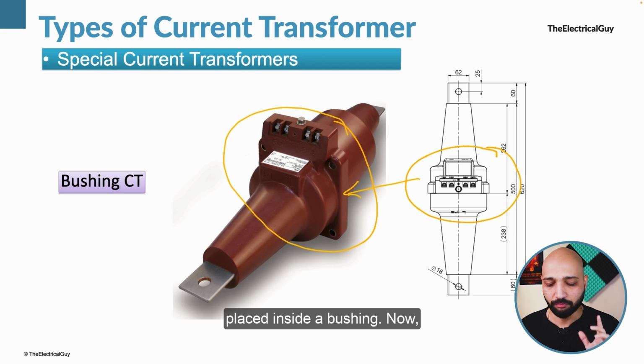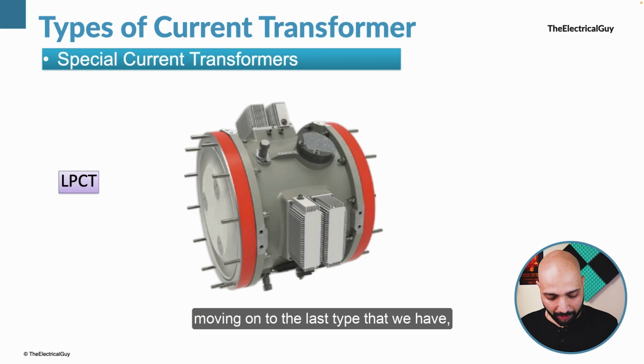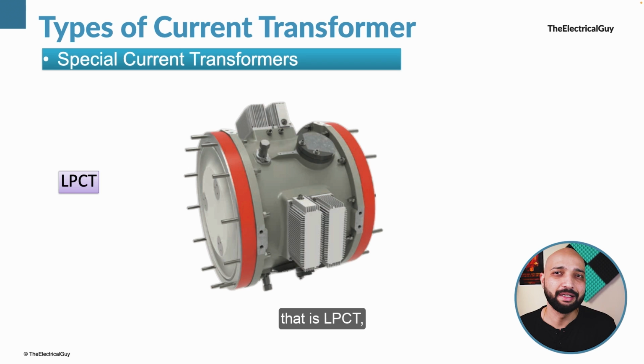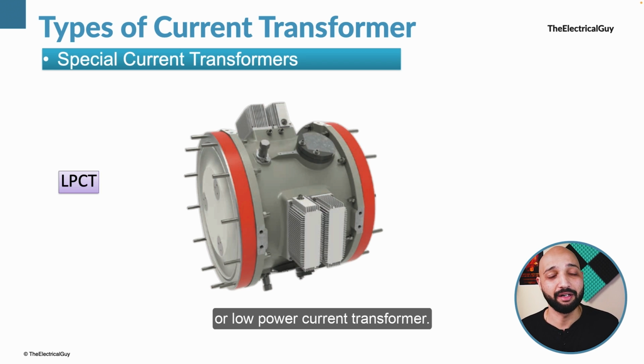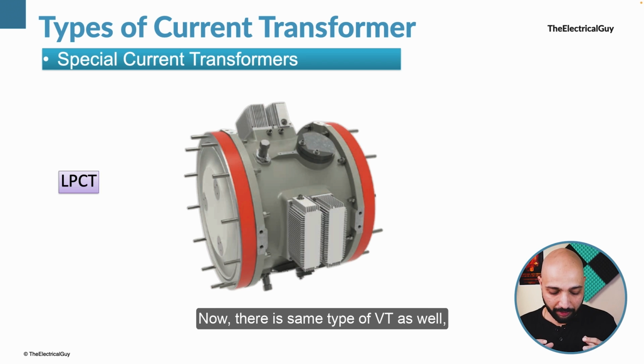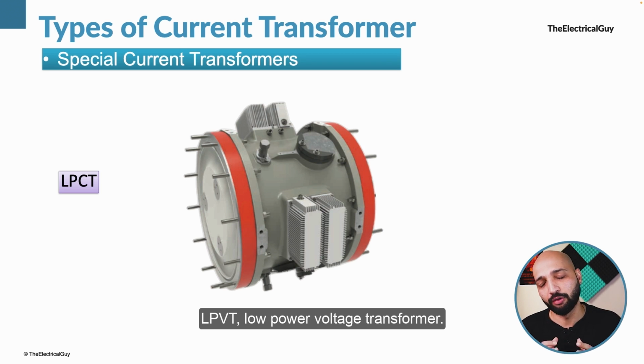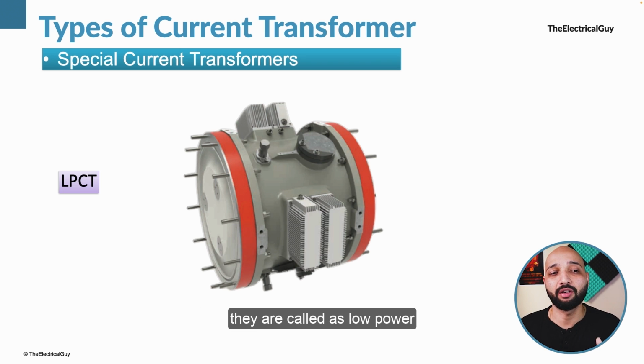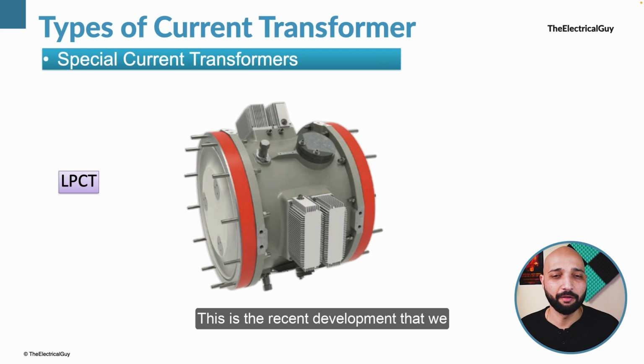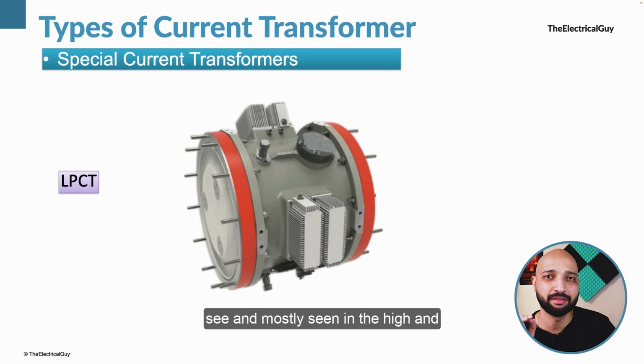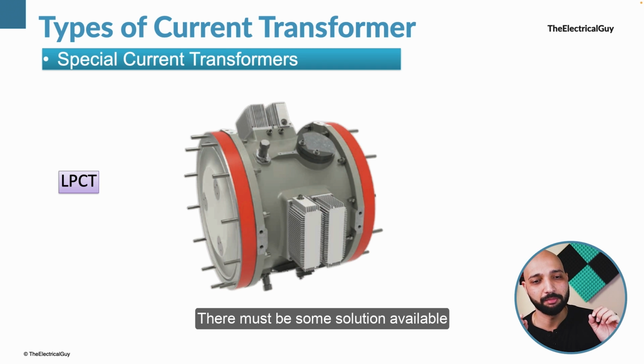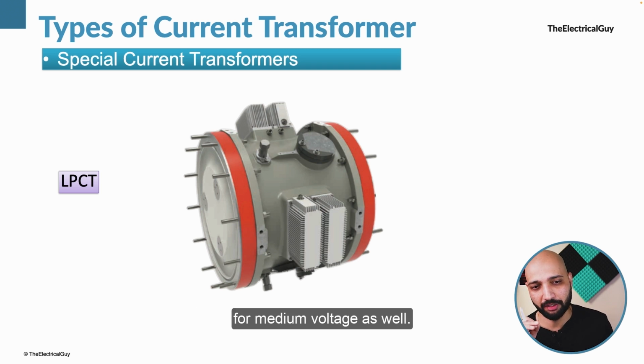Now, moving on to the last type that we have, that is LPCT or low power current transformer. There is the same type of VT as well, LPVT, low power voltage transformer. Put together they are called low power instrument transformers. This is the recent development that we see, and mostly seen in the high and extra high voltage GIS type switchgear. Now, there must be some solution available for medium voltage as well.